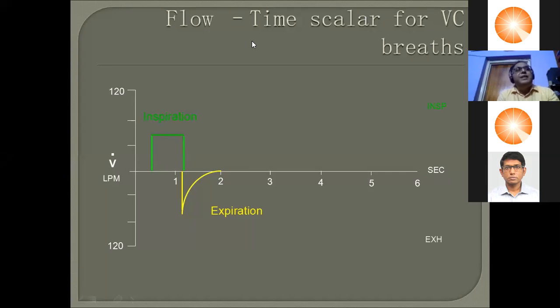So that means in 1 minute, how much? 500 into 60, so that's about 30 liters. So I need to generate a flow of 30 liters per minute and keep that flow on for 1 second. By doing that, I'll be delivering 500 ml. That simple calculation is done by the ventilator and it delivers the flow. So the flow remains constant through the inspiration. That is why in VC, as your inspiration starts, your flow goes up and then it stays constant until the end of inspiration, and then your expiration happens.